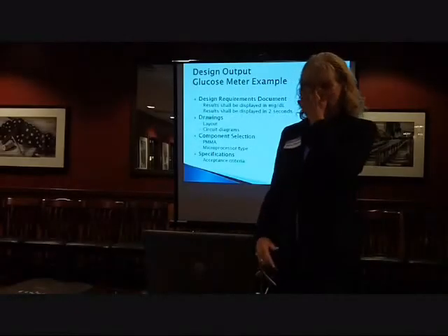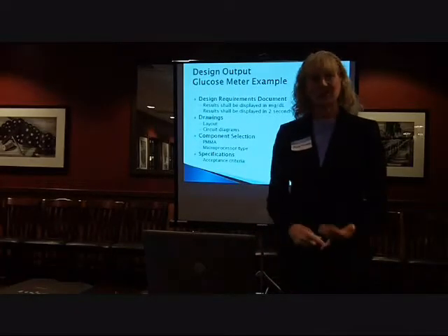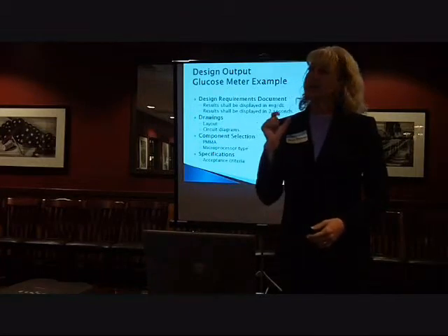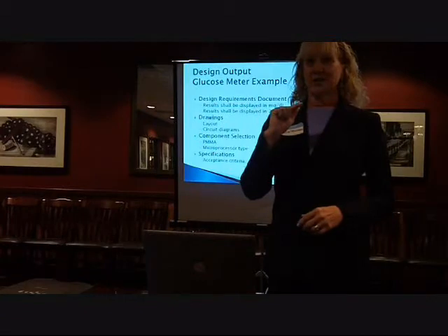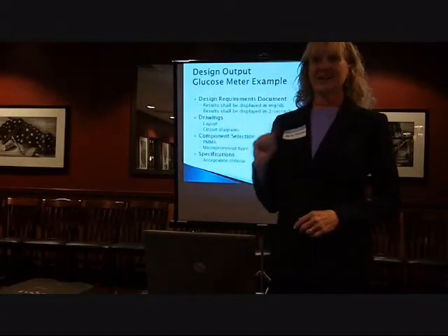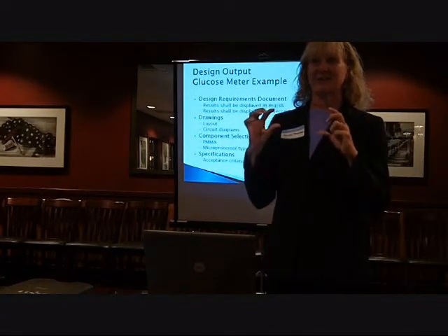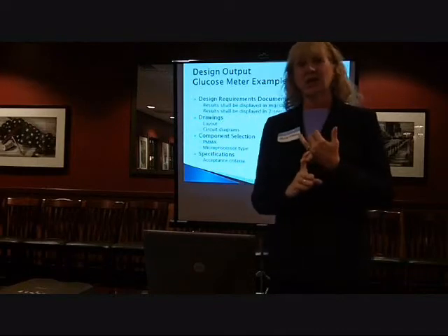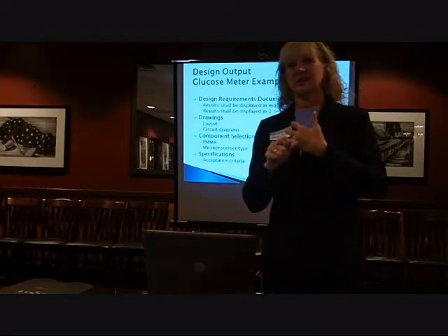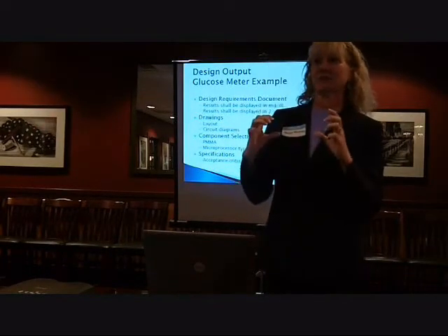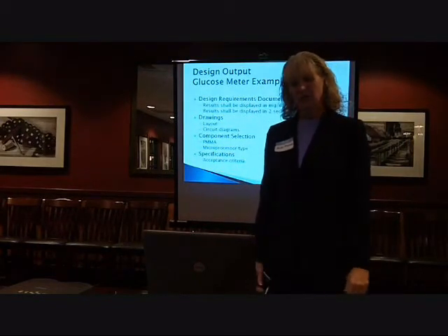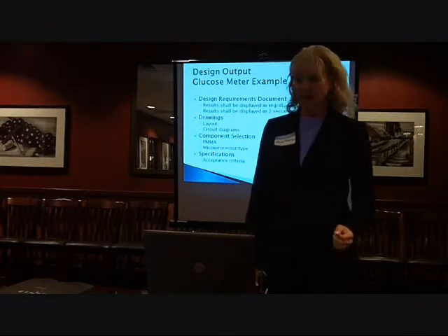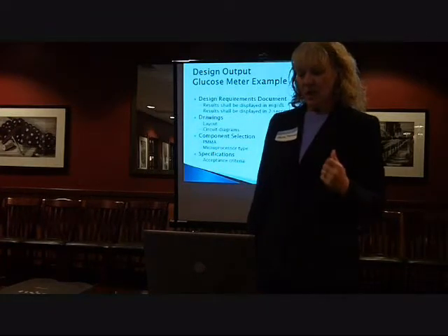Go on and on of all the different design requirements. Each one is indicated on its own line, because you're going to go back in and test this later. So you can't have, well, it needs to be in a range of 3 colors and it needs to have an alarm, all in one. You do them individually, and this will become important when you're doing your verification and validation activities.